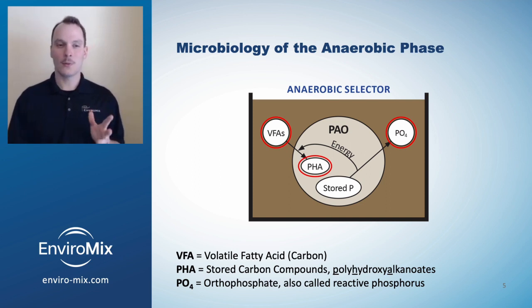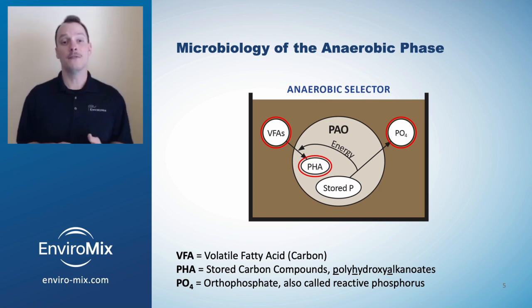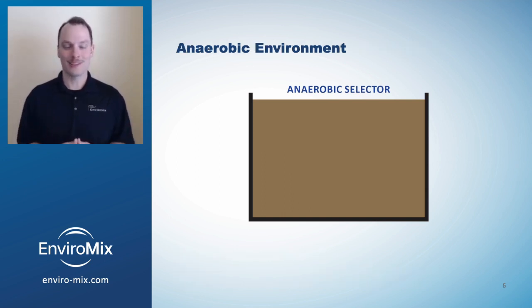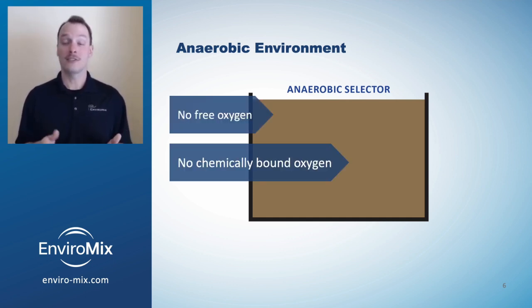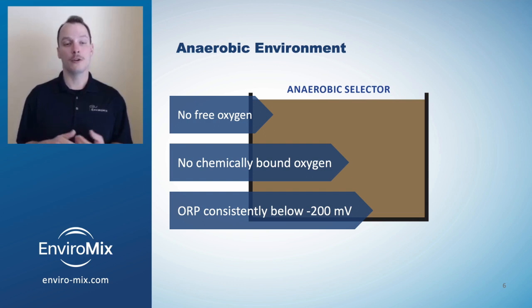So this is why it's vital that an anaerobic selector environment be truly anaerobic, and that it has sufficient VFAs to grow the PAOs. What is a truly anaerobic environment? An anaerobic environment means there's no free oxygen, nor any chemically bound oxygen such as nitrate, and further, when measuring the ORP, a truly anaerobic environment should stay below negative 200 millivolts.